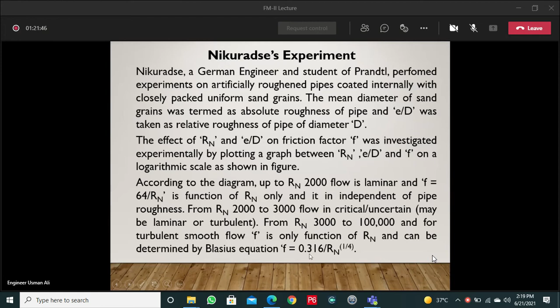According to the diagram, up to Reynolds number 2000, flow is laminar and f is 64 over Rn, and is a function of Rn only, and it is independent of pipe roughness, as can be seen in the diagram. From Reynolds number 2000 to 3000, the flow is critical or uncertain, may be laminar or turbulent. From Reynolds number 3000 to 100,000, there can be two possibilities. One is turbulent smooth flow, turbulent flow with smooth pipe. Friction factor is only a function of Rn and is given by the Blasius equation as given in this.